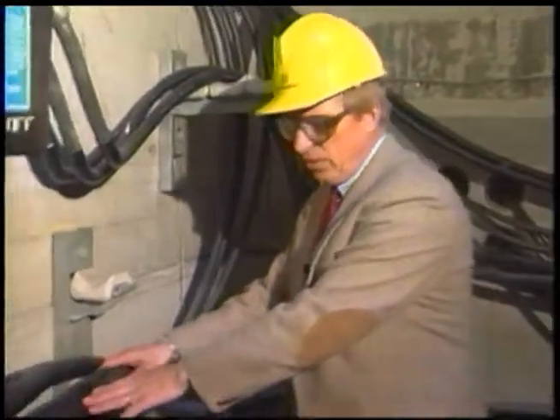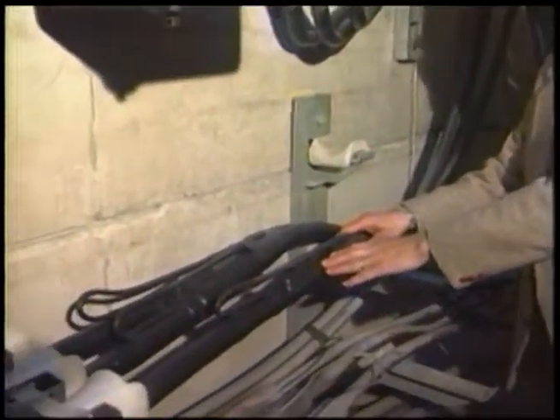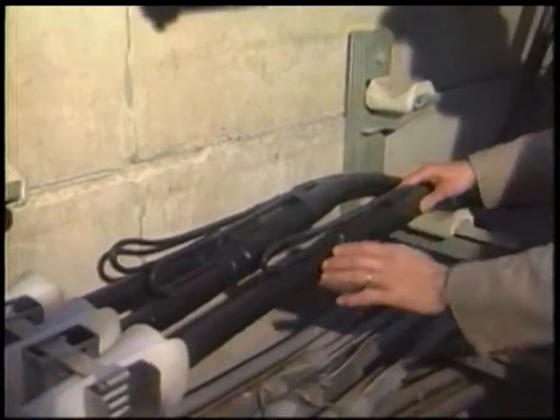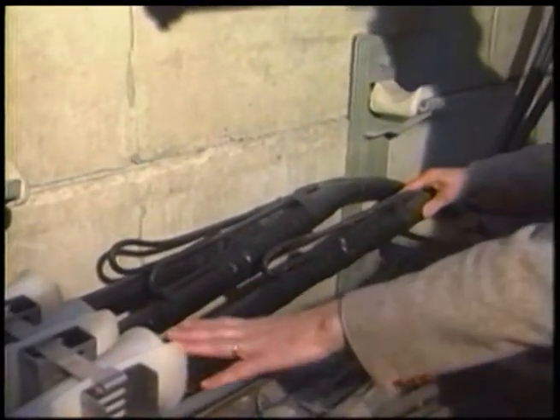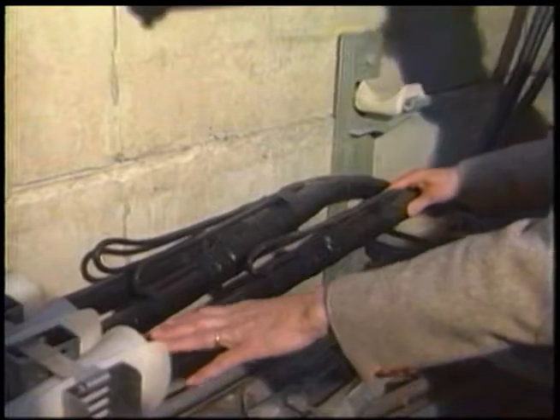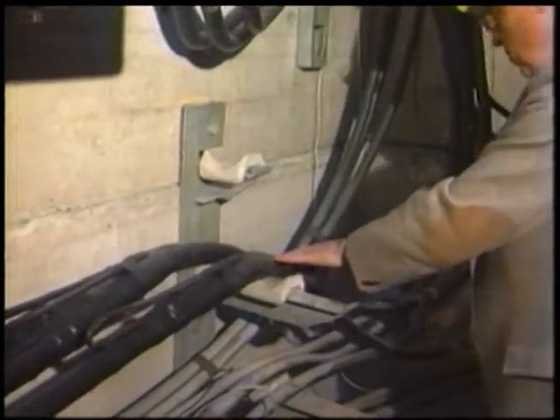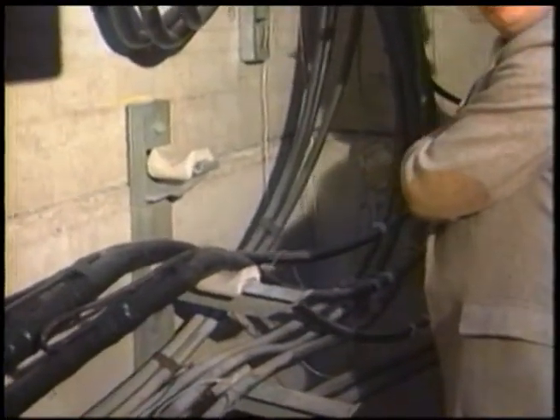Now, a question you may have: what happens if the ground blows free when a joint fails? Is the cable still grounded? The answer to the question is yes. This cable is coming from another manhole in which it is grounded. The cable on the other side is going to another manhole and it's also grounded in that manhole.